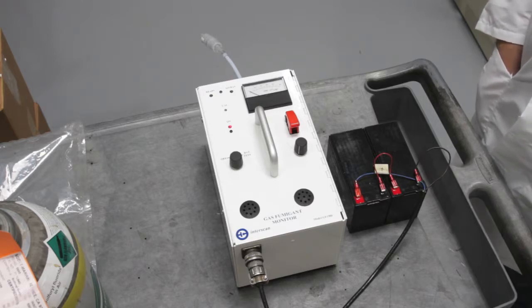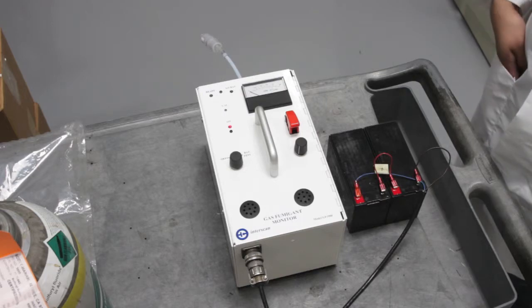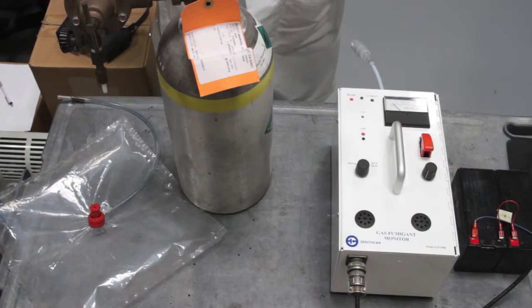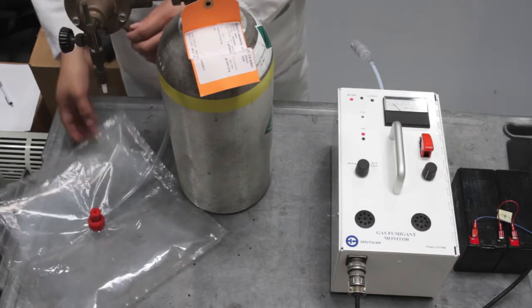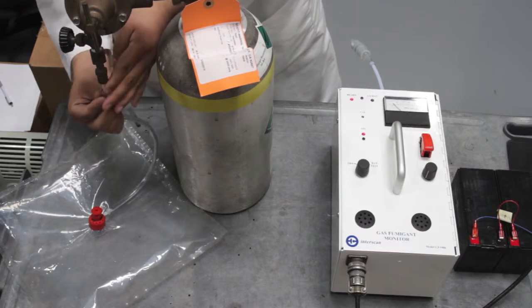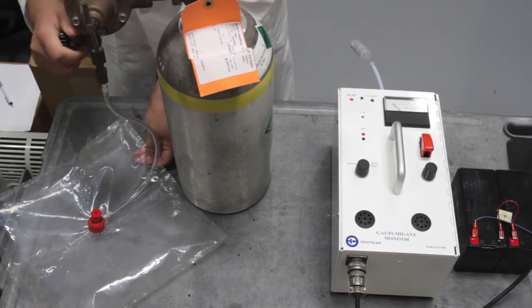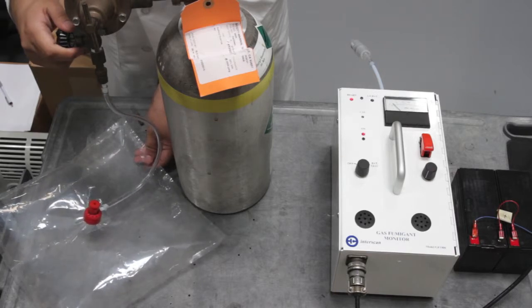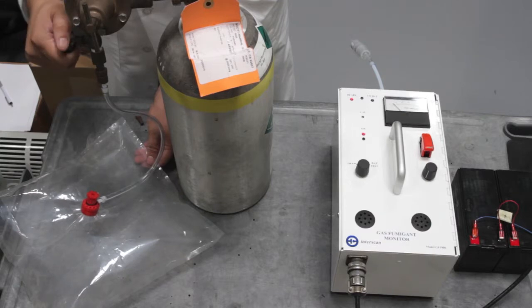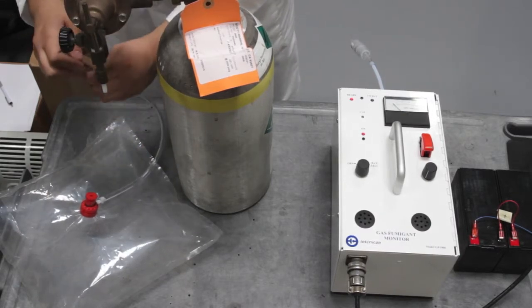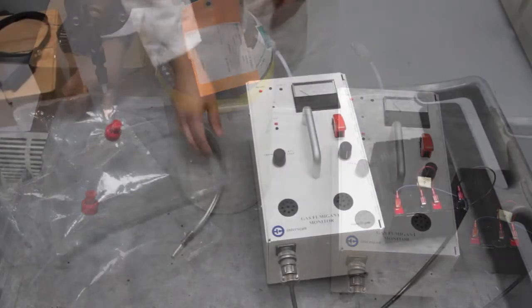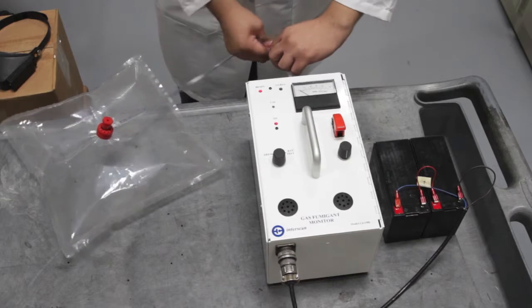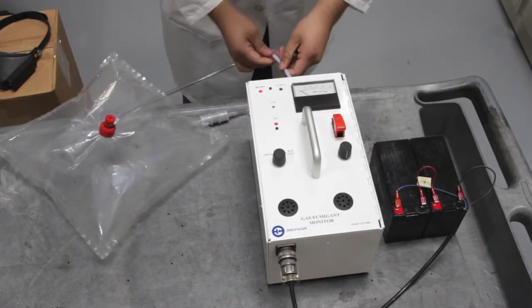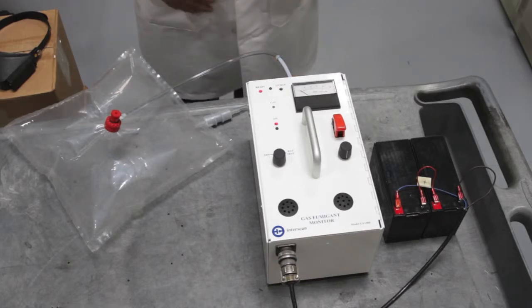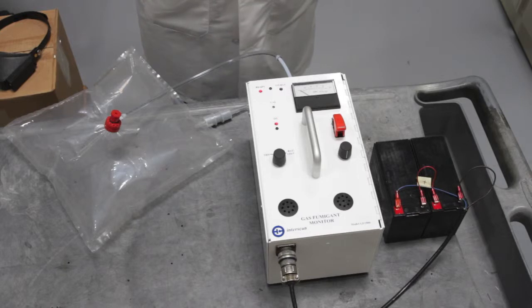You may only perform clearance or calibration once the monitor is stable. Now that the ready light is lit, we are ready for gas calibration. Fill a Tedlar sample bag with sulfuryl fluoride calibration gas. Use extreme caution when filling the bag so that it will not burst. Connect the bag to the inlet of the monitor. Allow the gas to flow for at least 3 minutes.